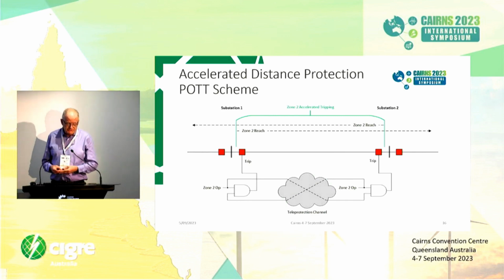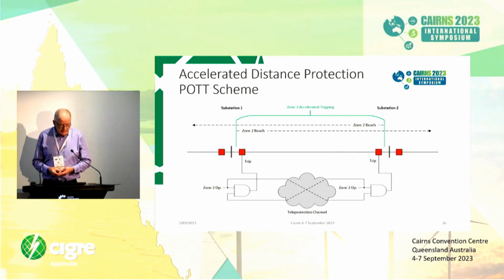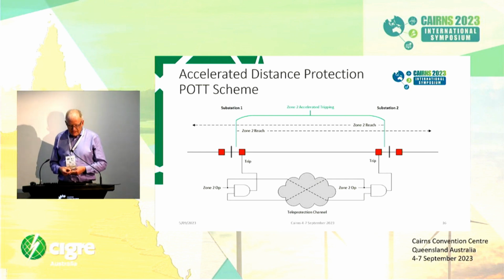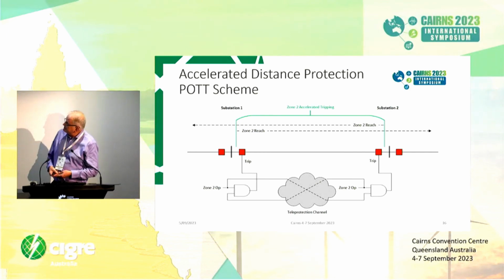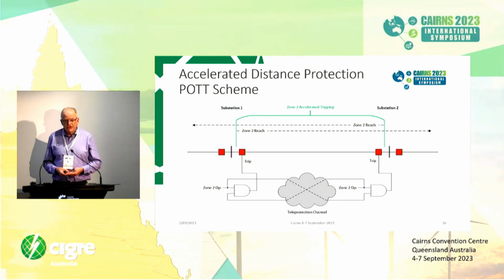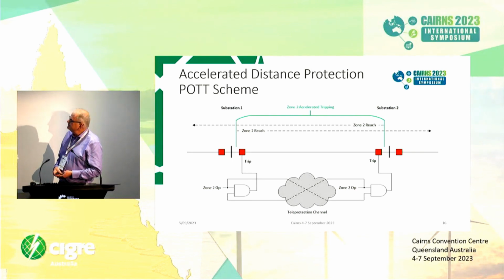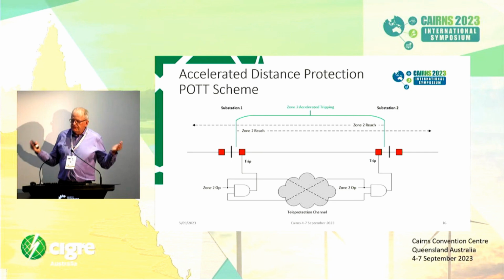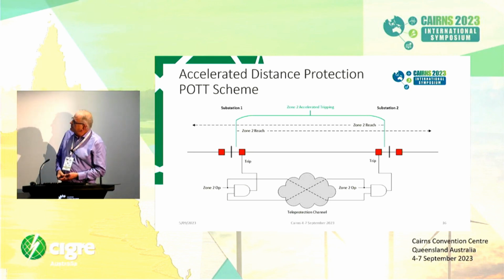So this is an example of a POTT scheme, a permissive overreach trip transfer scheme. The idea here is that we send the zone 2 protection pickup from, in this example, substation 1 to substation 2. At substation 2, we've got some logic to say that if you get a local zone 2 pickup and you get a remote zone 2 pickup, put it through an AND gate, then you can trip the circuit breaker instantaneously, knowing that the fault is actually on the transmission line you're trying to protect. As a backup, you've still got a delayed zone 2 pickup, so if the communications were to fail, like I said earlier, you'd simply delay the protection operation. But obviously that's great from a protection perspective with the communications because you're tripping instantaneously for faults in that transmission circuit.